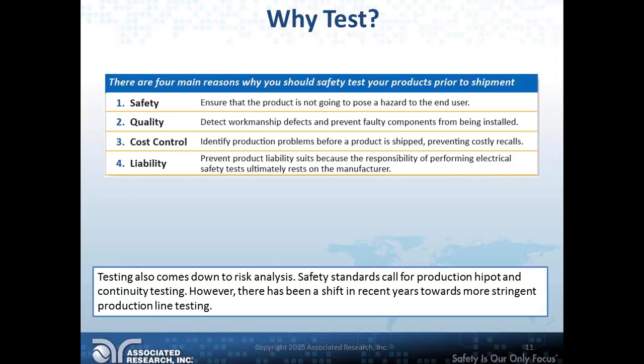Safety standards in recent years have shown a shift I've noticed. They mostly call for type testing, but they also say you need certain production line tests. Most standards say your production line testing is a hipot test and a simple ground continuity test, and that's it. More and more, though, I've seen manufacturers going through a risk analysis and determining they actually want to run more stringent tests on the production line, for one reason or another—maybe something in the manufacturing process, or something they're concerned about—so they cover their bases and run those tests.